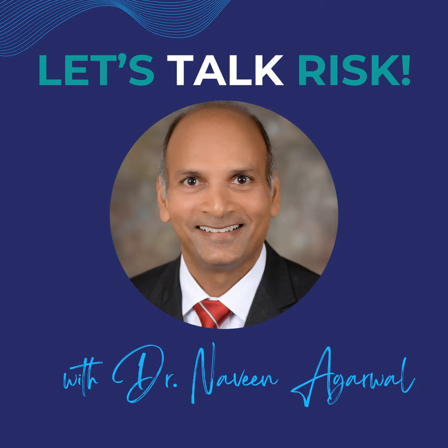So Phil, I think one of the things that you are struggling with, I suspect, is how to actually do this in practice. And do we need some identifiers for line items in our URRA and task analysis or FMEAs? I'll share what I have done in my practice. I've used good practices in database management, but find the key fields or elements that provide the anchoring of this traceability. And what I have used in my practice is the hazard ID as the connecting element across the board.